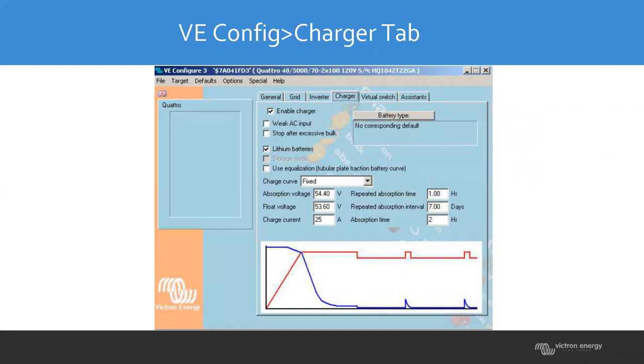So remember, it depends on what size generator you have. And for every one of these screens that you have to change, if you have 2 inverters, that's going to double that charge current. So if you have a multiple inverter charger setup, you'd want to figure out the max charge current of all units installed. On my generator, I like my generator to run about 50 or 60% of its rated capacity. And doing that figuring, it gave me about 50 amps DC into the batteries from the generator. Since I have 2 inverter chargers, I want 25 coming from one and 25 coming from the other.